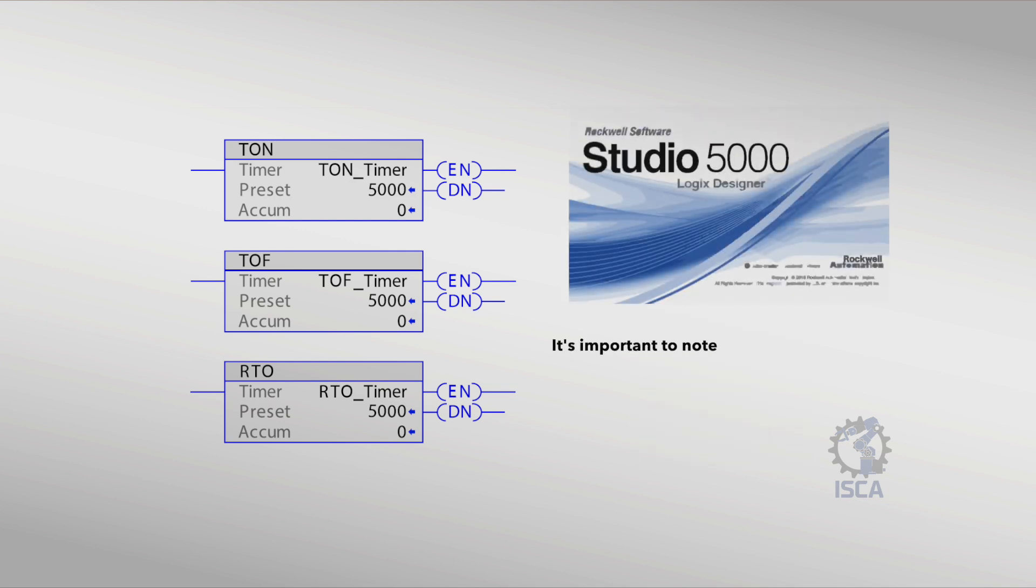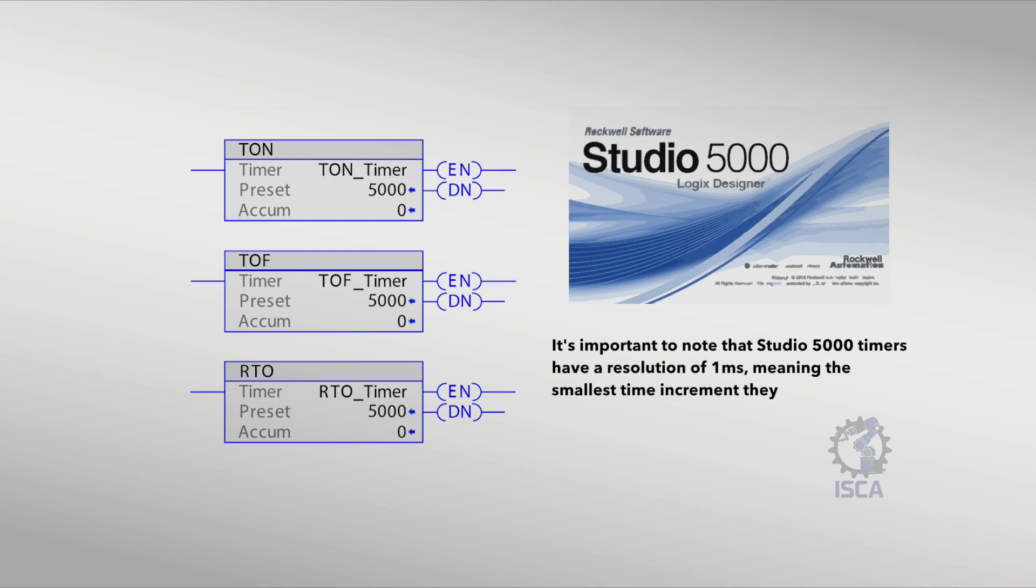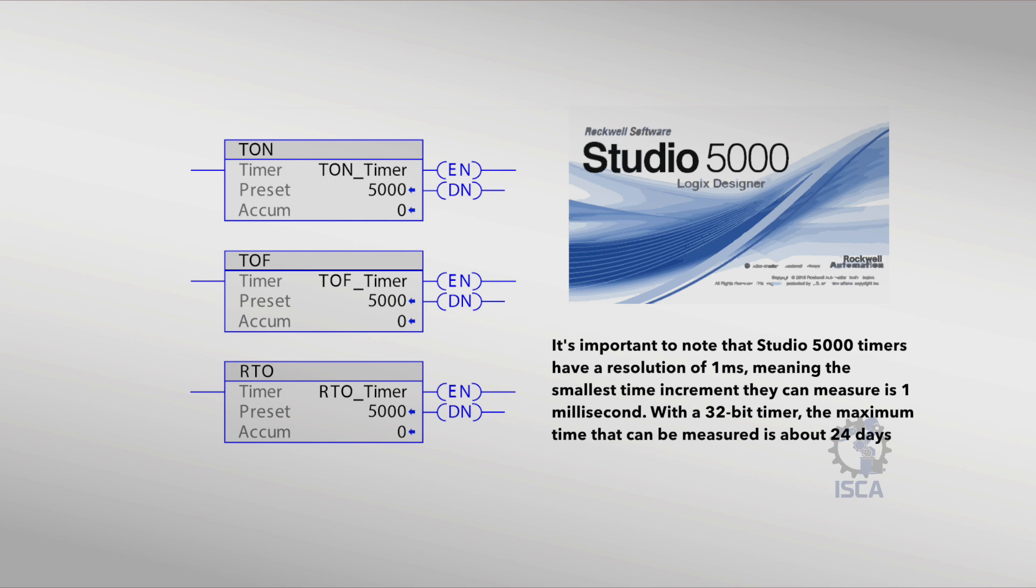It's important to note that Studio 5000 timers have a resolution of 1 millisecond, meaning the smallest time increment they can measure is 1 millisecond. With a 32-bit timer, the maximum time that can be measured is about 24 days.